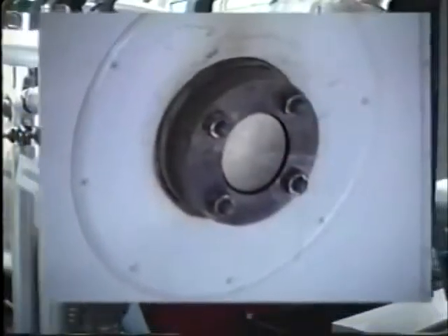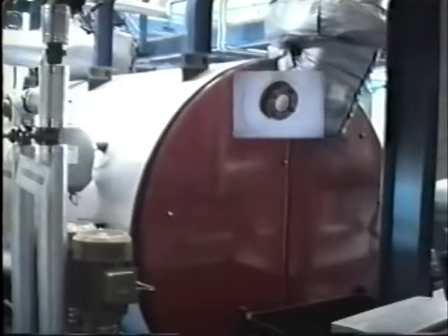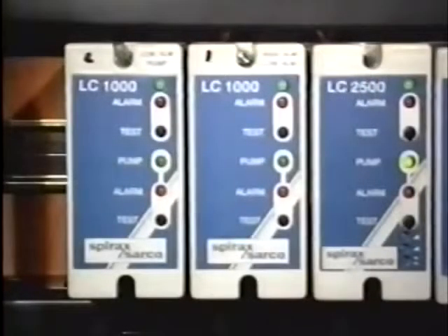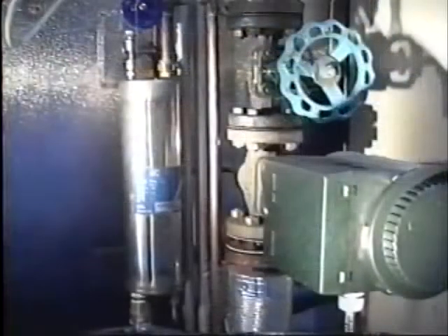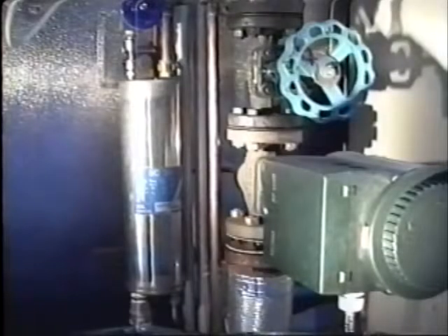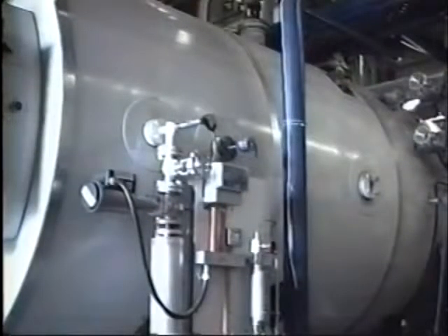We have seen the way in which water behaves in steam boilers under normal conditions, high and peak steam demands, and have examined the effect of normal and high TDS. We hope we have also demonstrated just how important it is to have precise, accurate level controls and alarms, as well as providing a system to control the level of total dissolved solids as closely as possible to the boiler manufacturer's recommended level.